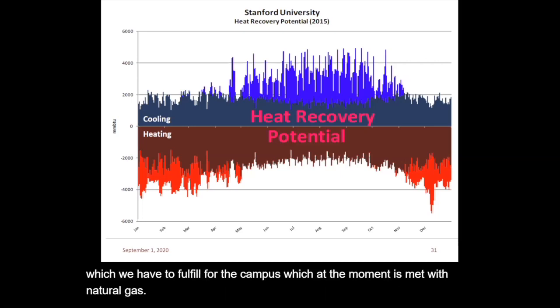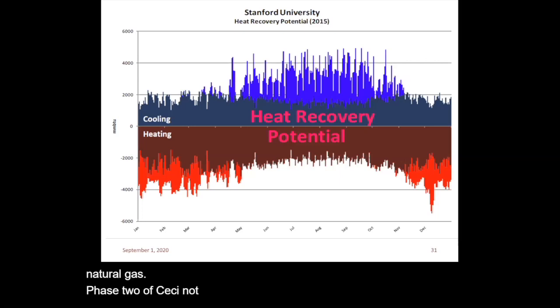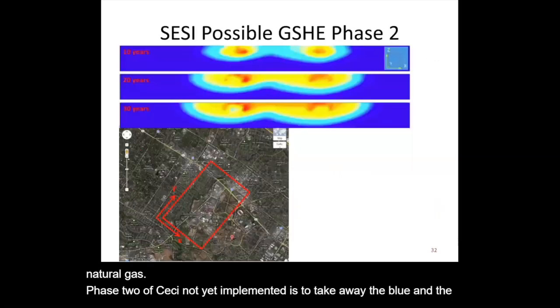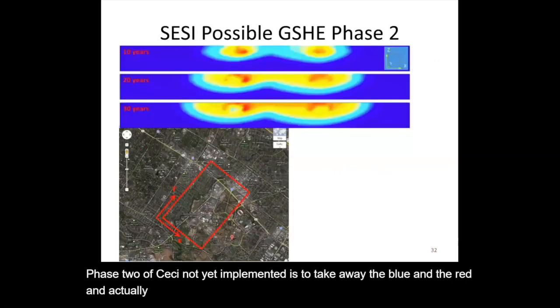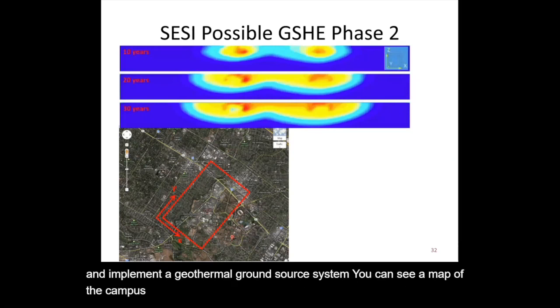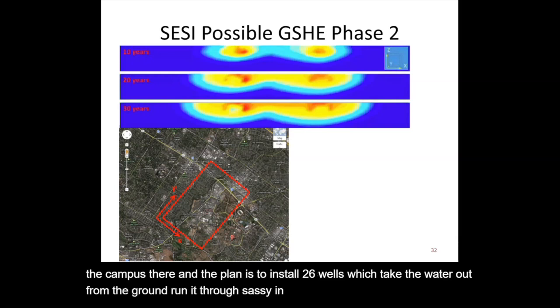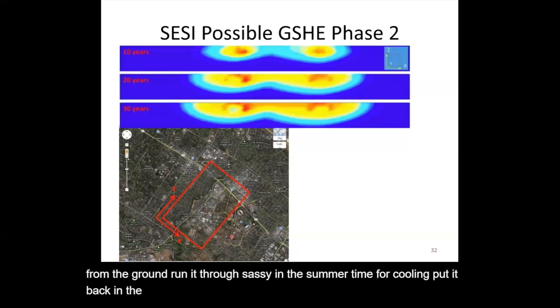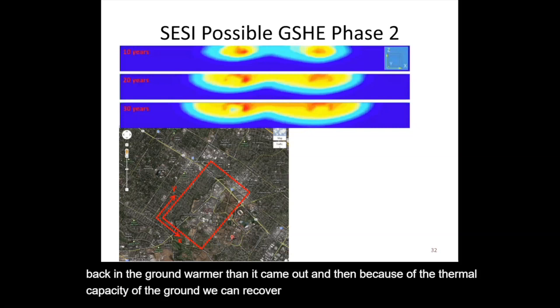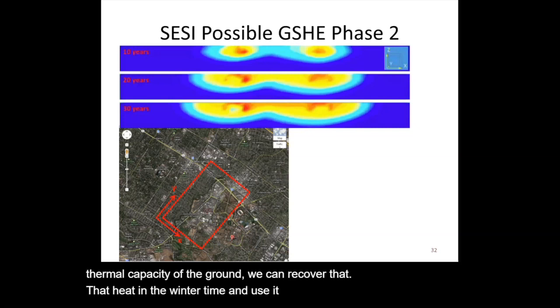So phase two of SESI, not yet implemented, is to eliminate the blue and the red by implementing a geothermal ground source system. Here's a map of the campus. The plan is to install 26 wells that take water out of the ground, run it through SESI in summertime for cooling, and put it back warmer than it came out. Then, because of the ground's thermal capacity, we can recover that heat in wintertime and use it in place of natural gas.